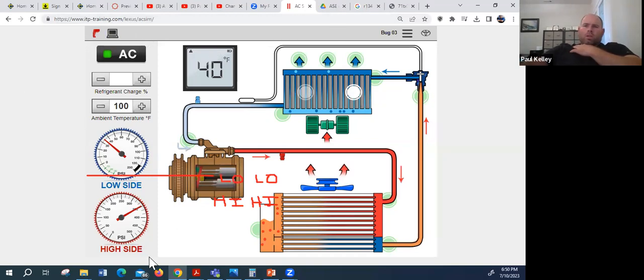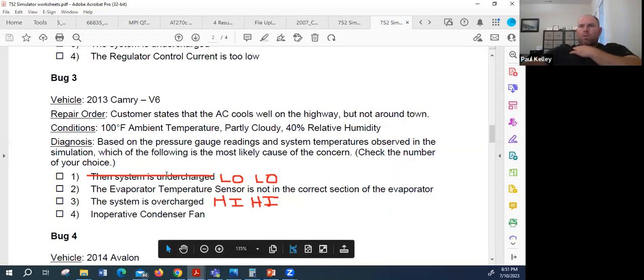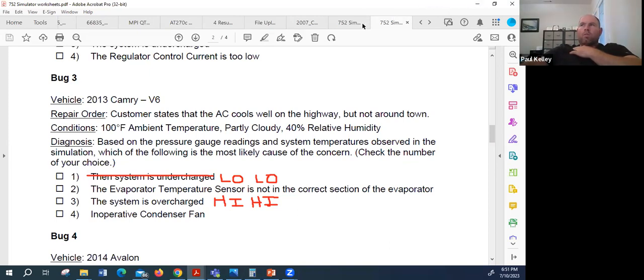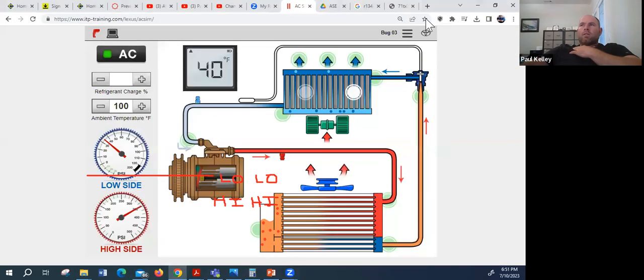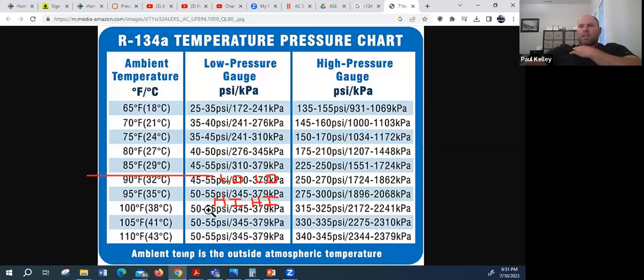So this one though, we haven't really got a ton of traction on. We agree it's not undercharged. Do you feel like it's overcharged? Is it high on both the high and the low side? Because if you look, you're at 35 and 350. If we look at our chart at 100, we should be at like 55 and 315 to 325.